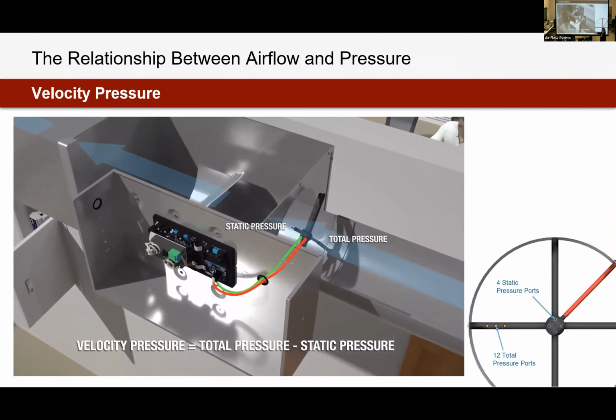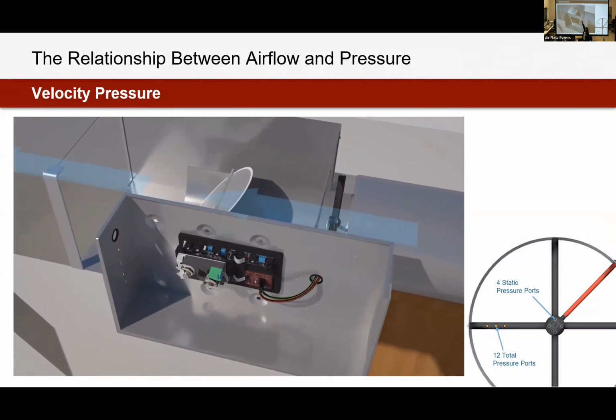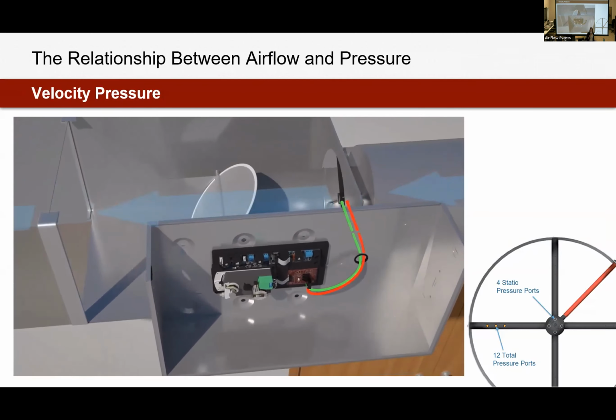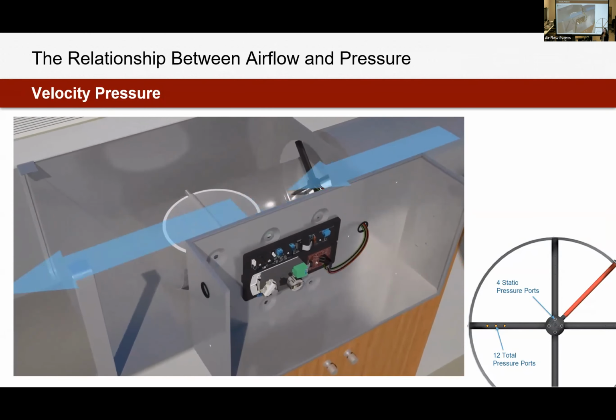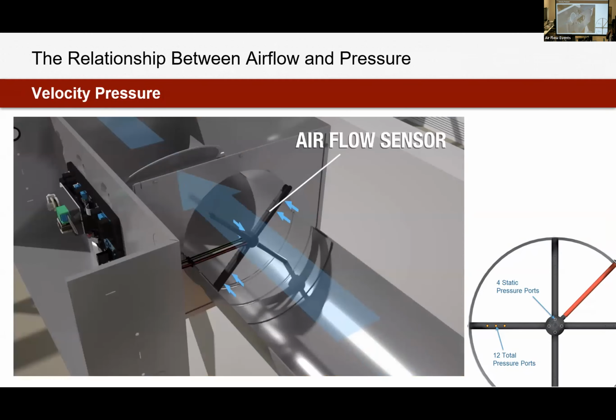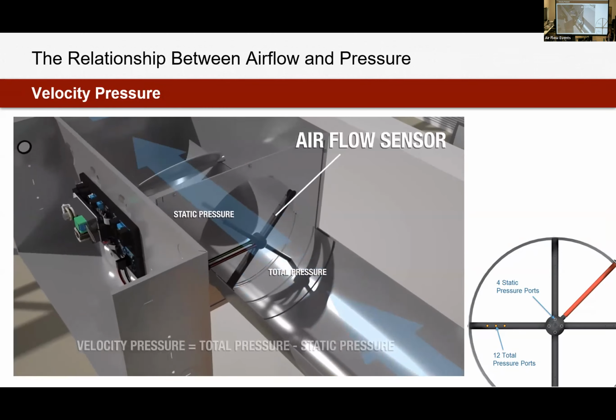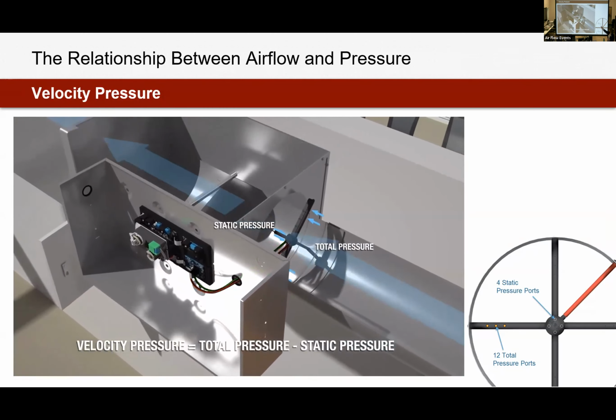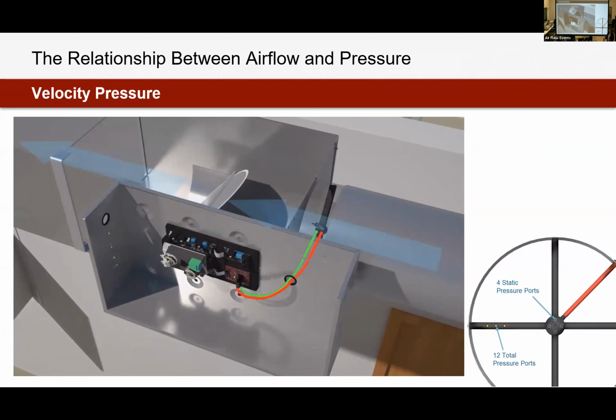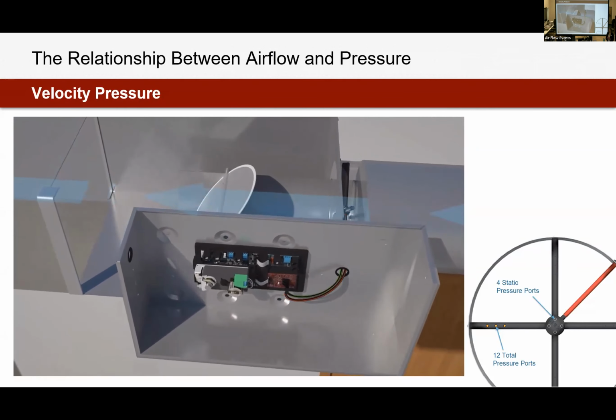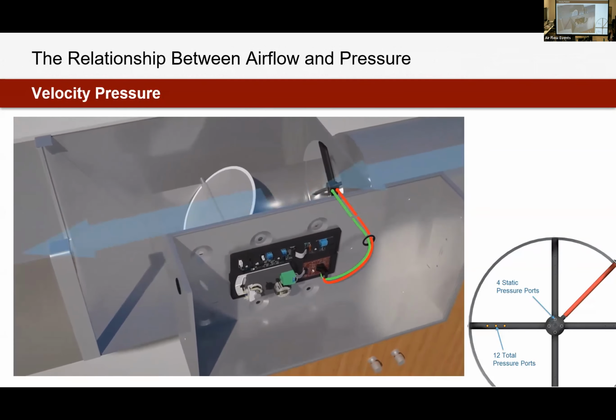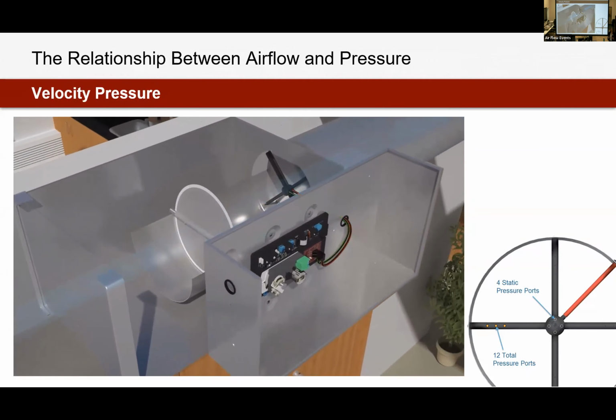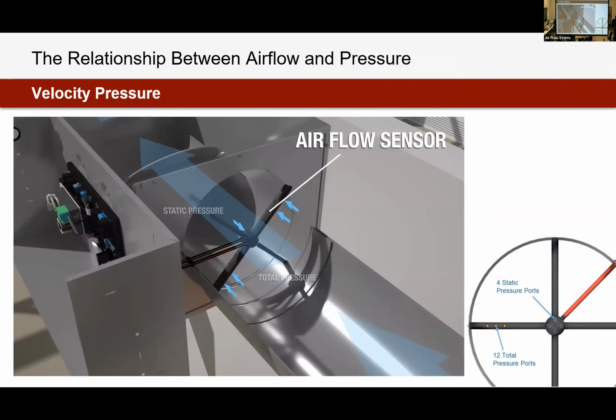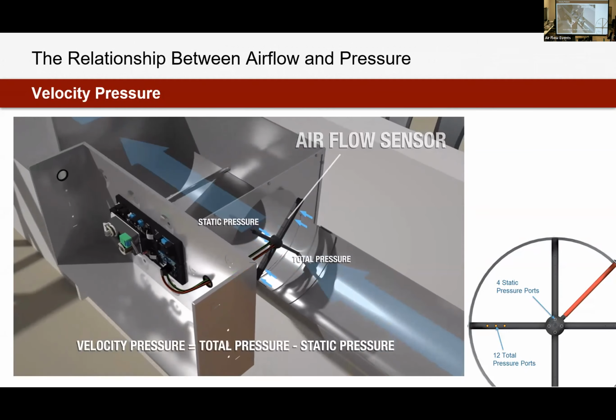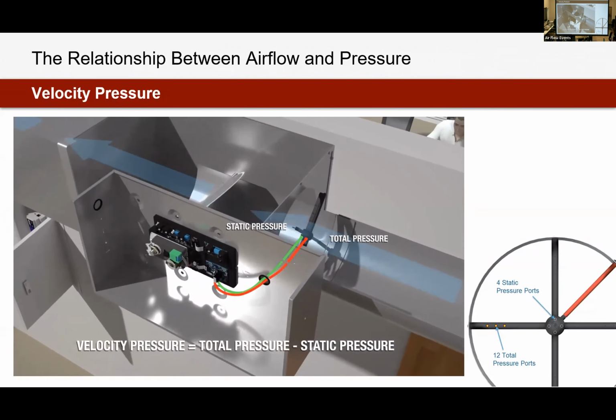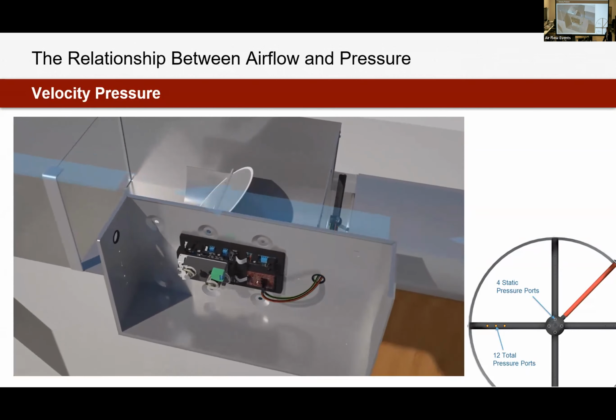Hidden on the back side of the sensor, you can see the little arrow right there. On the back side of the sensor, we're able to pick up a static pressure in the duct. There's no influence of velocity passing over the sensor. It's hidden in the back there. So what we're actually sending to the controller is a total pressure and a static pressure. But what we ultimately want to get to is that velocity pressure. Velocity pressure is very difficult to actually measure itself. So we're using that pressure relationship to find a velocity pressure, which can then be correlated to our airflow.